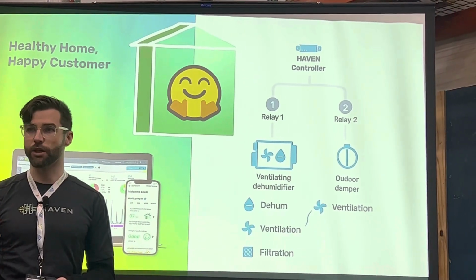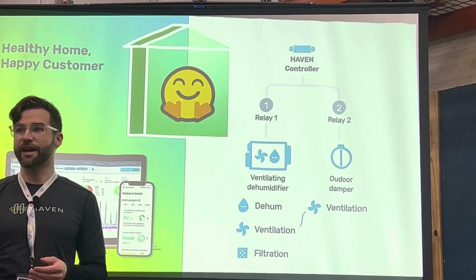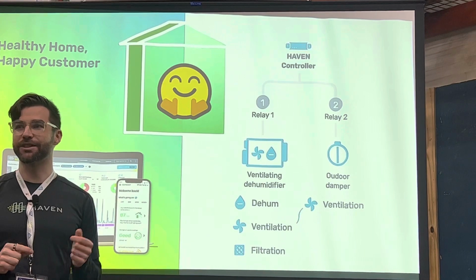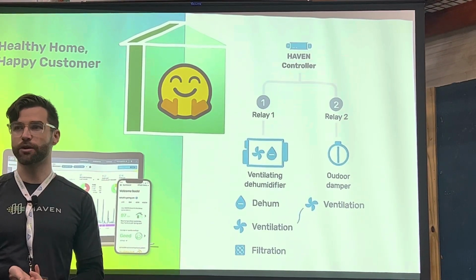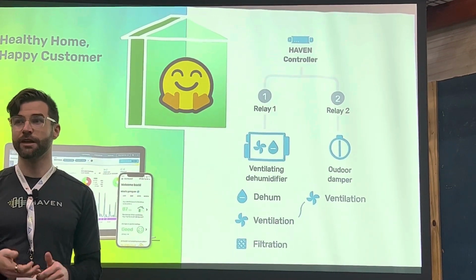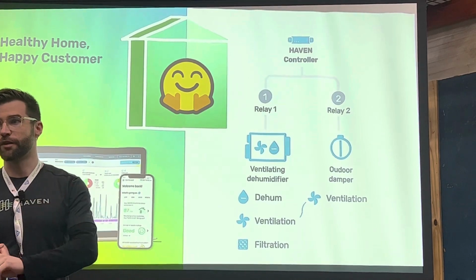It's essentially adding load to do the work of dehumidification. So now your air conditioner is sized better. Ed, you might be cringing at what I'm saying here, but there is some ability to actually improve the comfort and better adjust the oversized equipment to meet the comfort needs of a home through installing this without having to rip out and replace that oversized piece of equipment.